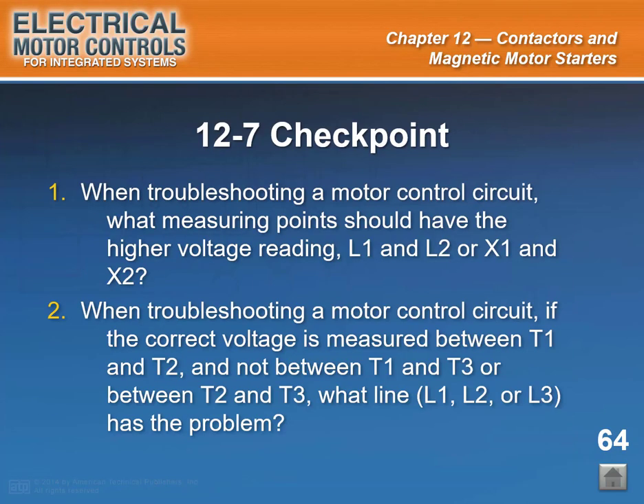Slide caption: 12-7 checkpoint. When troubleshooting a motor control circuit, what measuring points should have the higher voltage reading, L1 and L2 or X1 and X2? When troubleshooting a motor control circuit, if the correct voltage is measured between T1 and T2, and not between T1 and T3 or between T2 and T3, what line, L1, L2, or L3, has the problem? End of slide 64.